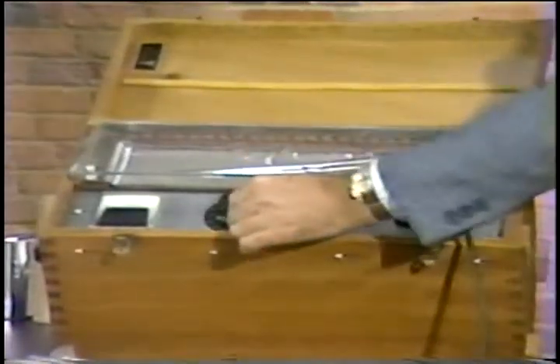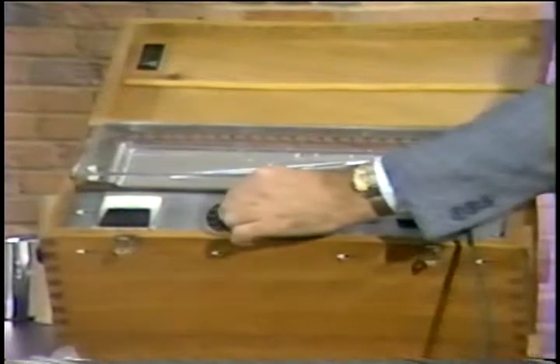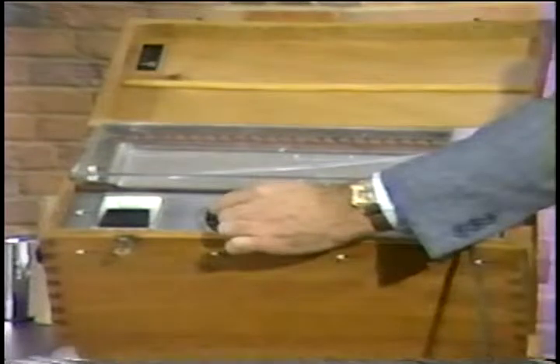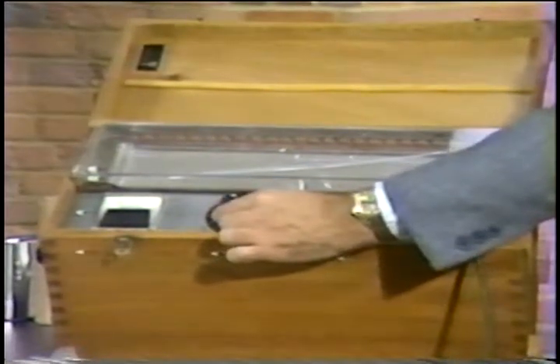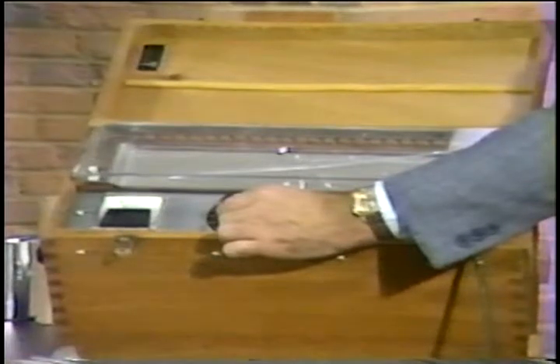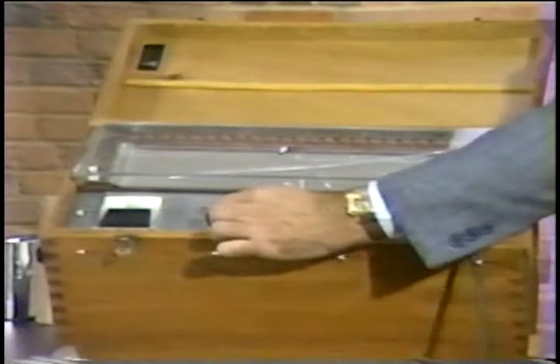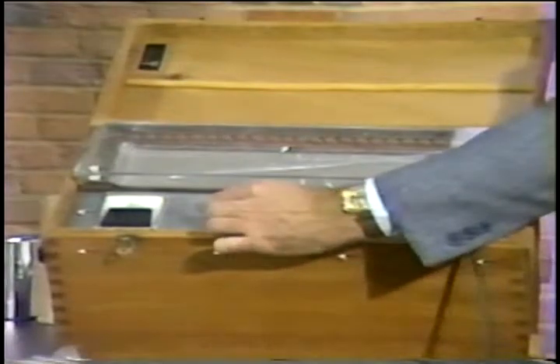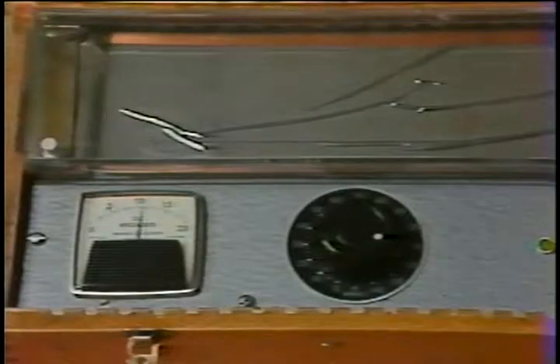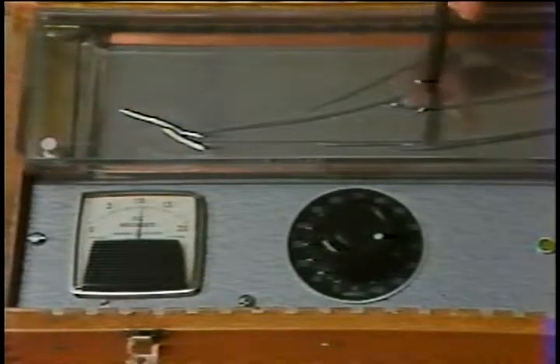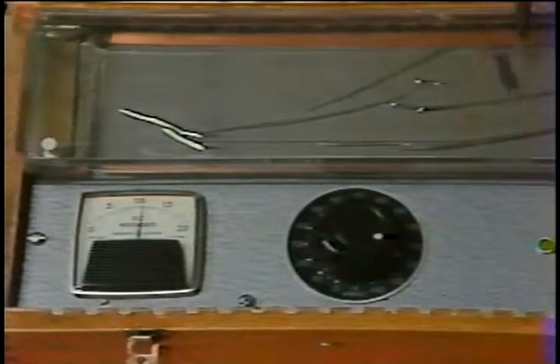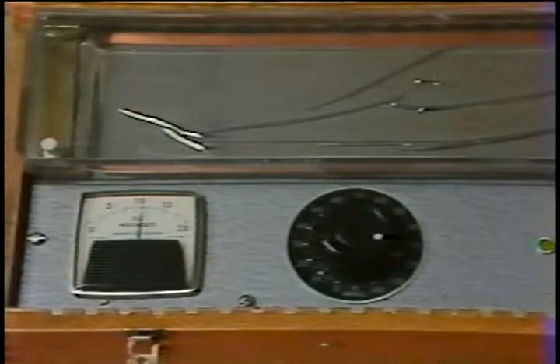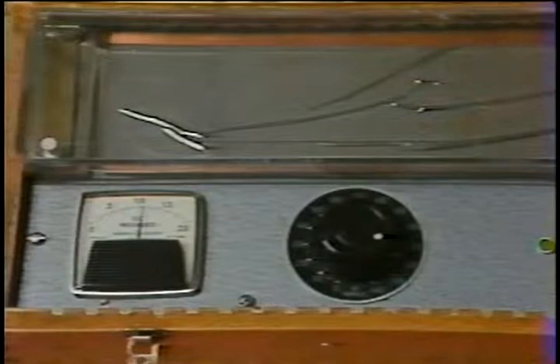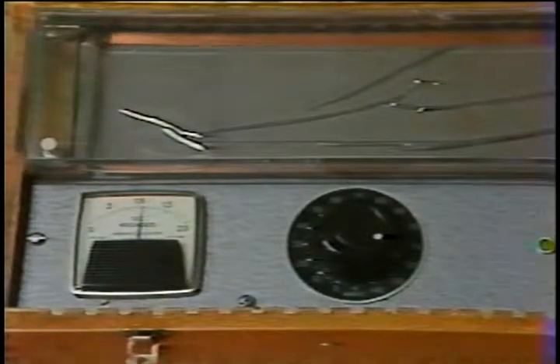Okay, let's try this again. Increase it to 50 volts, 100 volts. There's a few clearings. 500 volts. 800 volts. 1,000 volts. You see that all of the defects which I created in this film have been cleared out. The clearing process is a very important part of the operation of a metallized capacitor because it allows it to be operated at very high stresses.